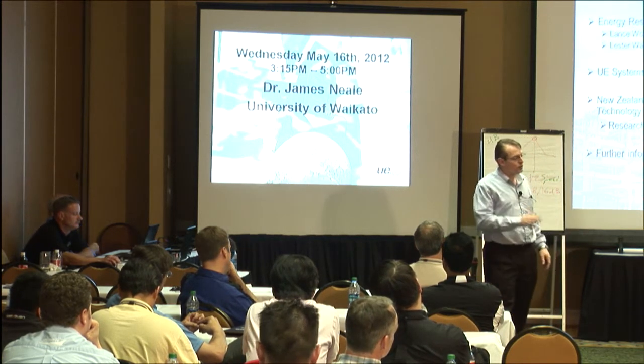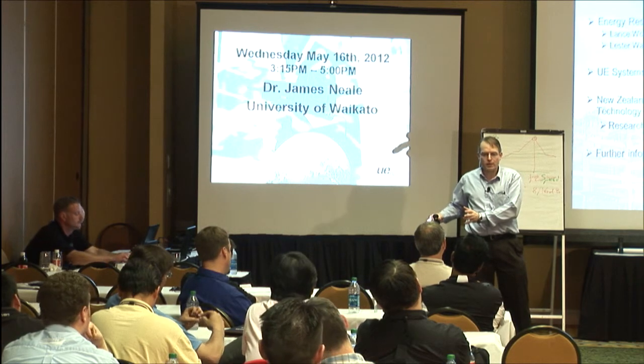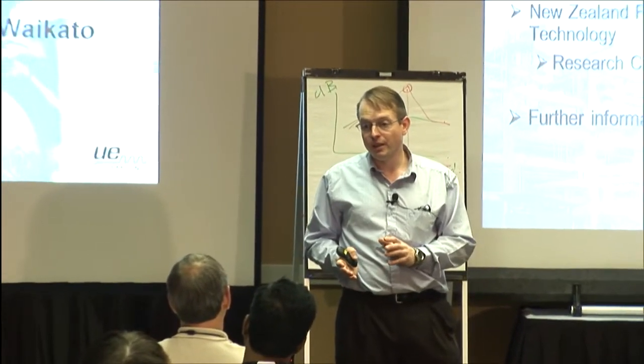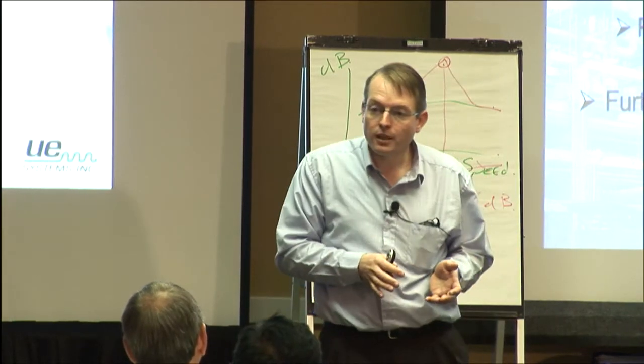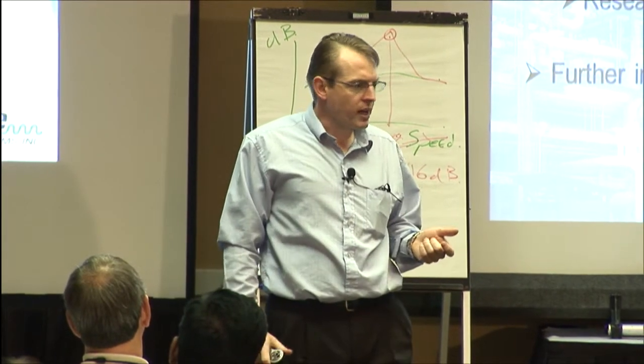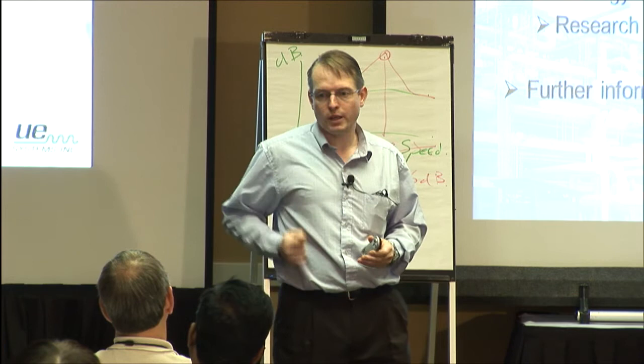The only thing you've really got to be careful of is whatever that motor is then driving, okay? If it's a pump, obviously, as that speed's going up, you're putting more flow, more head, and same with a fan, and so you have to be a little careful. And granted, you've got more load on the bearing, but the point is this. Above all else, with the sensitivity dial on the gun, you can use your ears as a pretty good judgment as the first warning, okay?